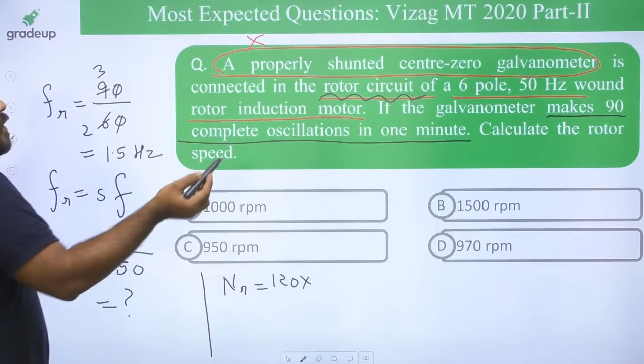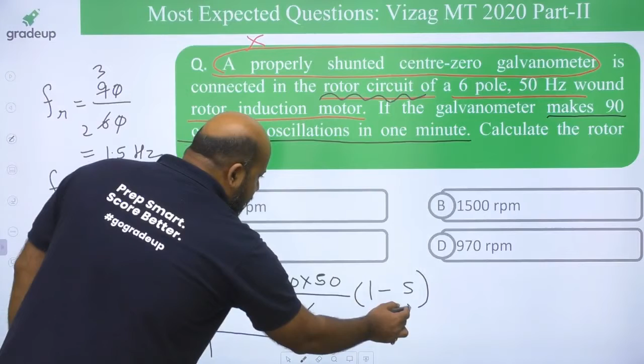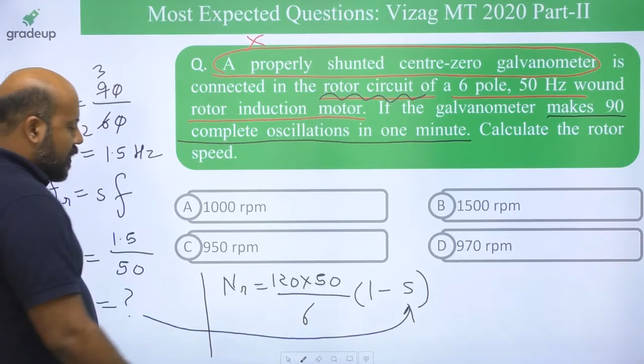And from here you can calculate the rotor speed NR as 120 times F, where F is 50 hertz, divided by P, the number of poles, given as 6, times (1 minus S). So put this value of S from here and tell me what is the value of the rotor speed you are getting. Everybody just tell me yes or no. What is the value of rotor speed you are getting? Tell me quickly. I think you must be getting 970 RPM.